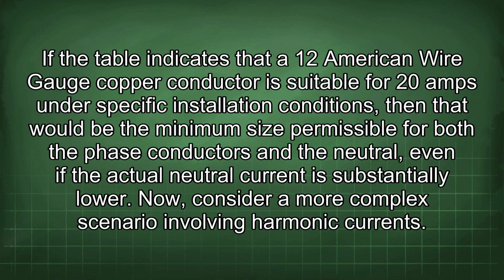If the table indicates that a 12 American wire gauge copper conductor is suitable for 20 amps under specific installation conditions, then that would be the minimum size permissible for both the phase conductors and the neutral, even if the actual neutral current is substantially lower.